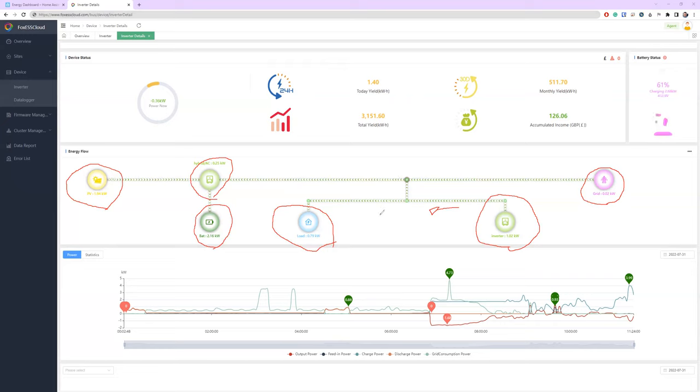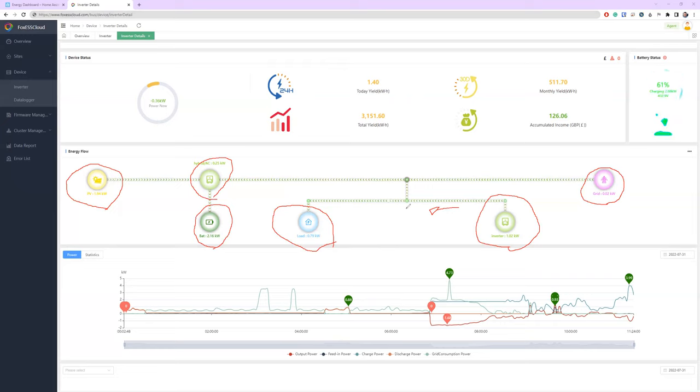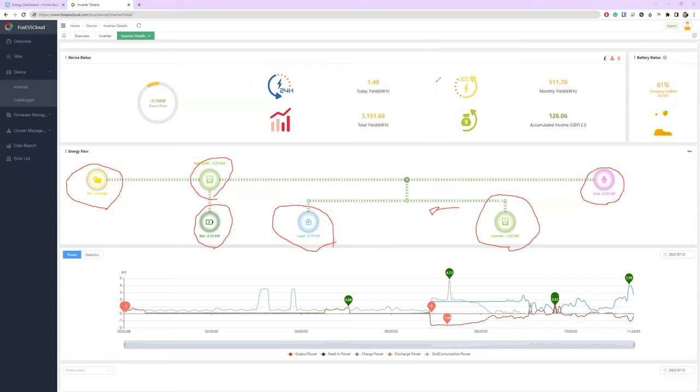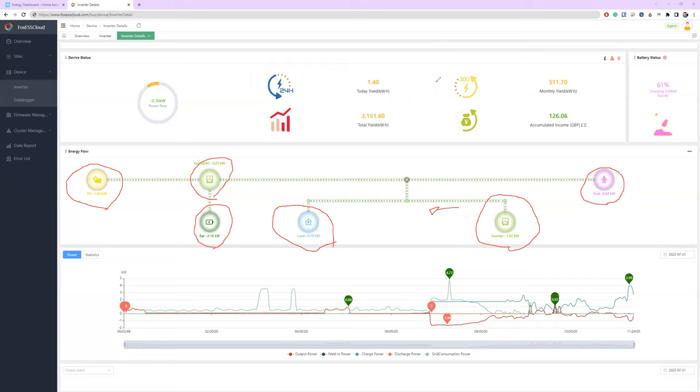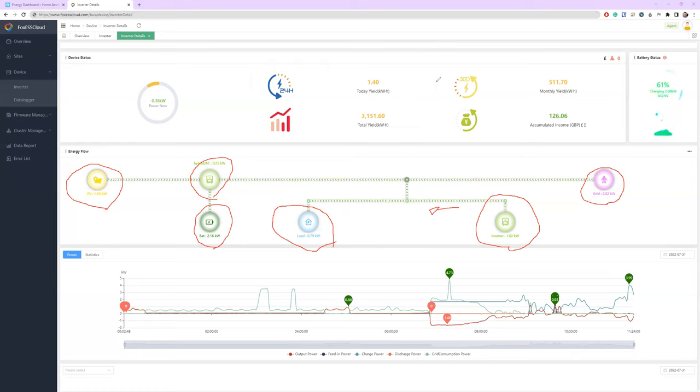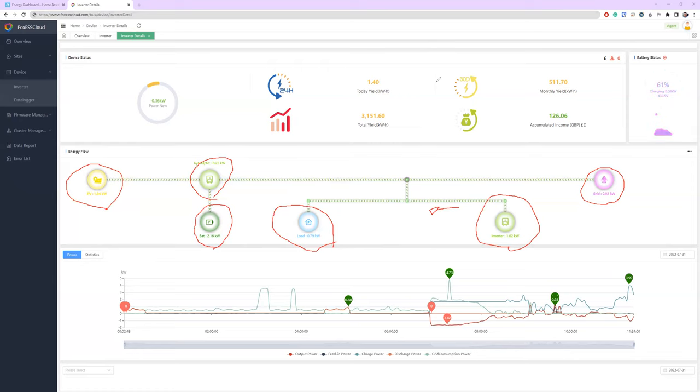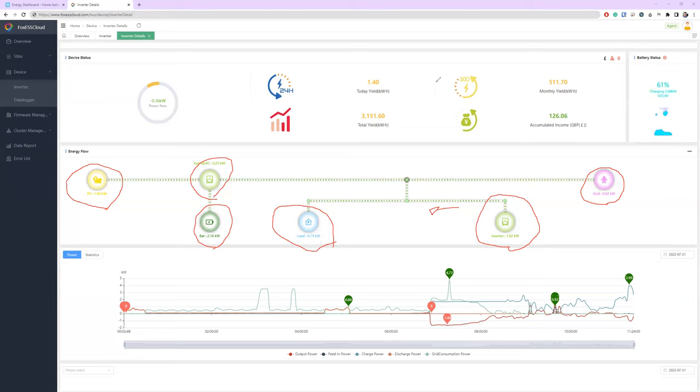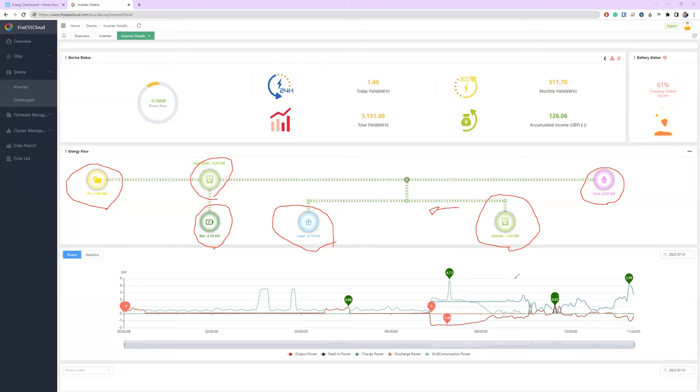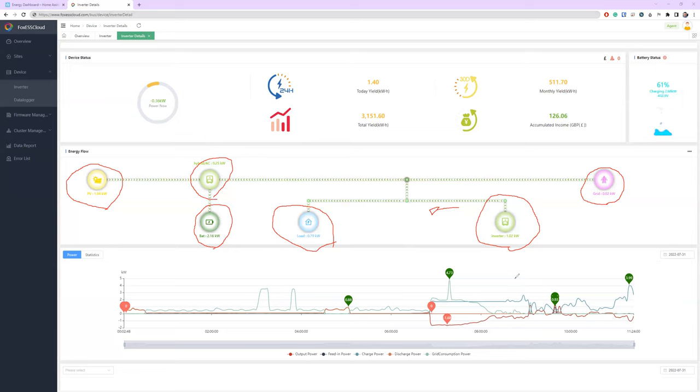Now what you need to understand about the FoxESS or the way that FoxESS reports data, which is not uncommon - it is this way for many solar inverter brands - is that it is sending a packet of data every few minutes. Depending on what your inverter is configured to, by default it is every five minutes. Some folks have reduced their poll level to 60 seconds or 120 seconds, but you are only getting a pulse of data that includes the current values.